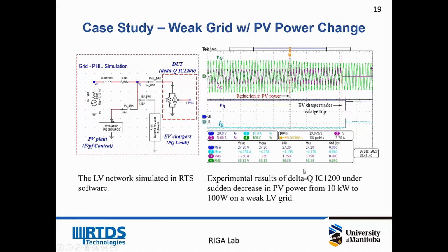It also can test with a very complicated grid network. For example, here is a weak grid with PV power change. So we can simulate a grid network in the software side. For example, here the grid has a very large inductance, and we also have a PV energy source to inject power into the grid. Then the hardware will interact with the grid here. This one is the model inside the RSCAD, and we have a terminal connecting to the hardware through RTDS.